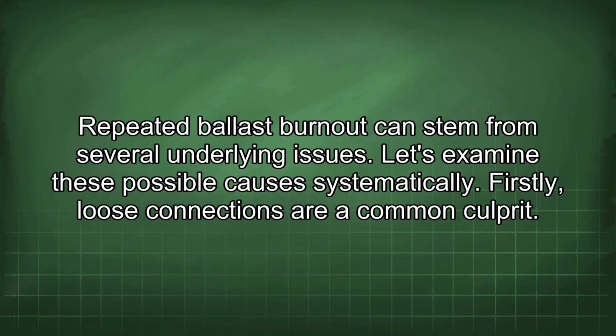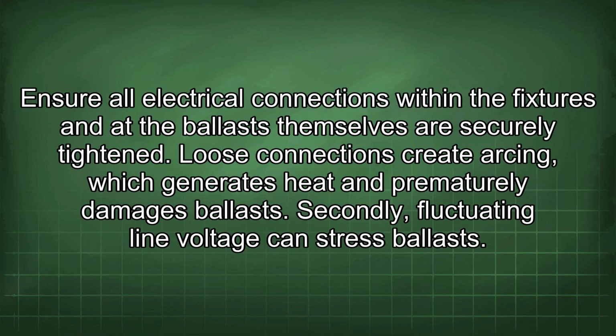Repeated ballast burnout can stem from several underlying issues. Let's examine these possible causes systematically. Firstly, loose connections are a common culprit. Ensure all electrical connections within the fixtures and at the ballasts themselves are securely tightened. Loose connections create arcing, which generates heat and prematurely damages ballasts.